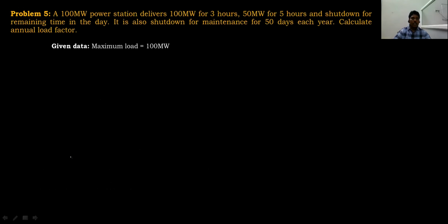Next problem. A 100 megawatt power station delivers 100 megawatts for 3 hours, 50 megawatts for 5 hours, and is shut down for the remaining time in a day. It is also shut down for maintenance for 50 days each year. Calculate the annual load factor. In a year we have 365 days. Out of 365 days it is shut down for 50 days. Therefore the plant operates for 315 days in a year, into 24 hours.